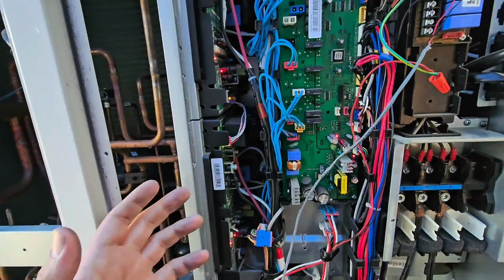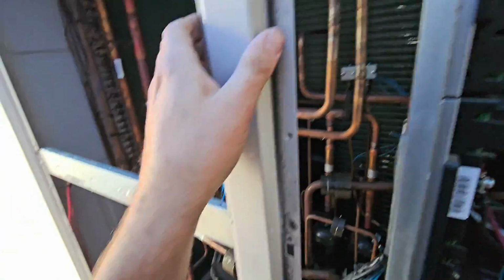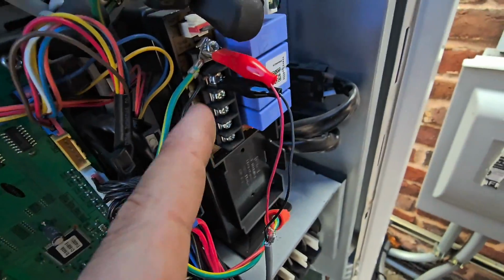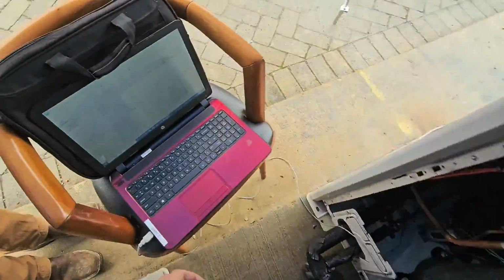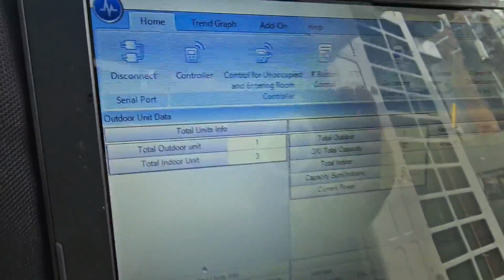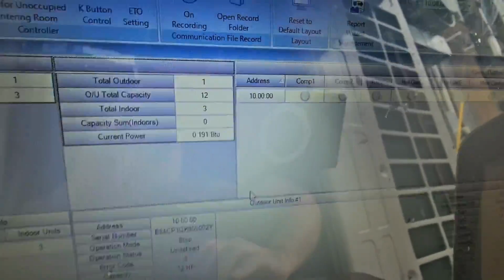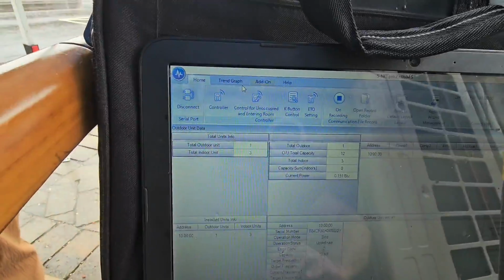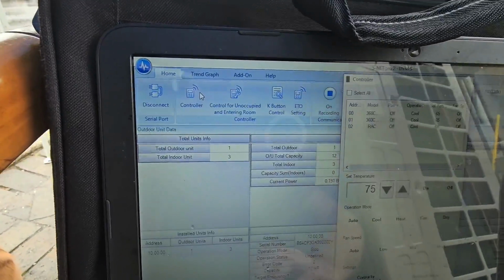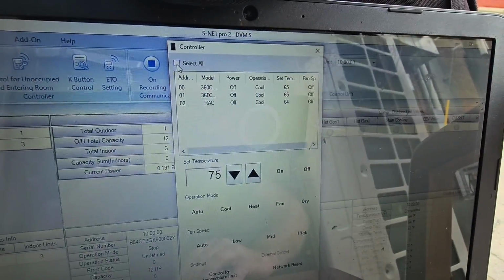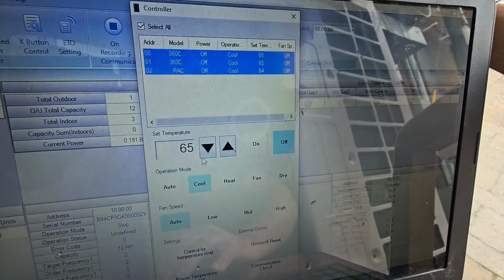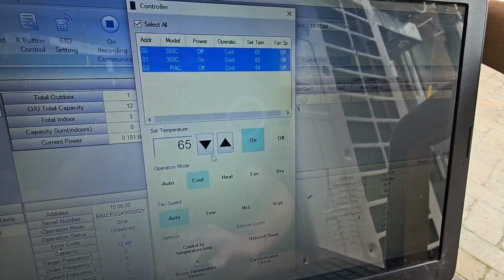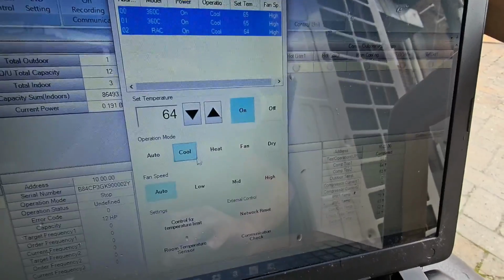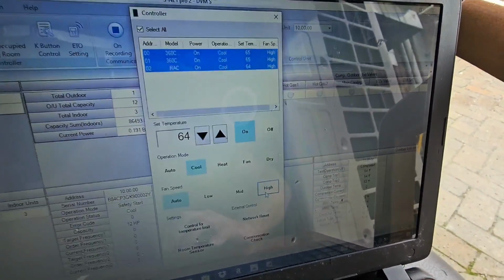Now, before we move forward, I want you to see the error code that I had. So I've got the SNET tool hooked up, and it's hooked up to the F1 and F2 terminal. And I've got it connected. You can see it's connected, and you can see we've got 3 indoor units, 1 outdoor unit. We're going to go up here to where it says controller. We're going to click that button. Then we're going to select all of our indoor units, and we're going to turn them all on. 65 sounds good, or 64 on cooling, fan speeds on high.